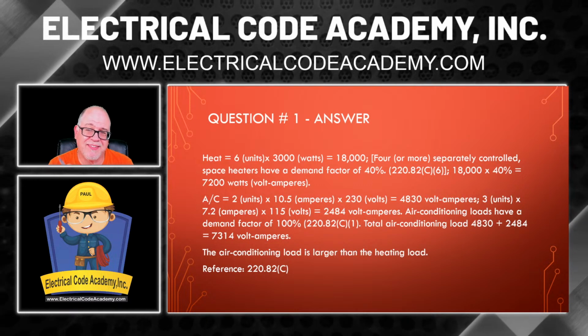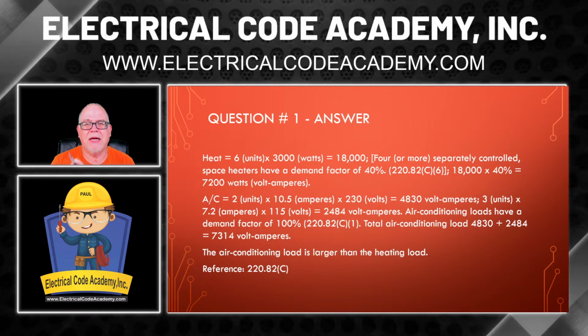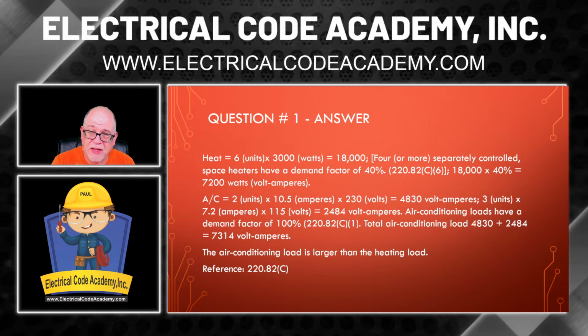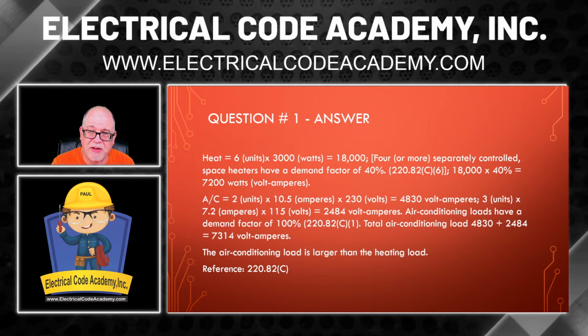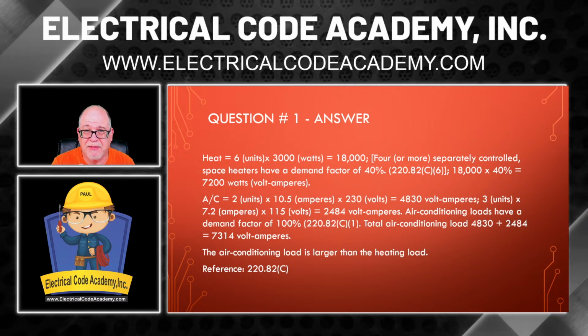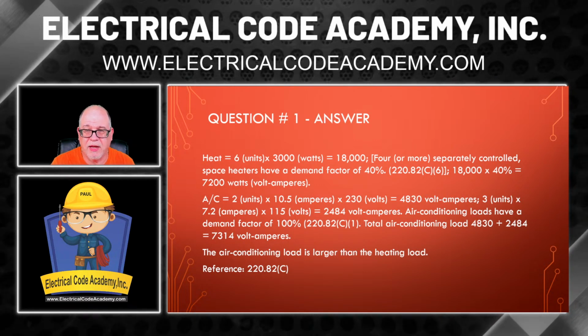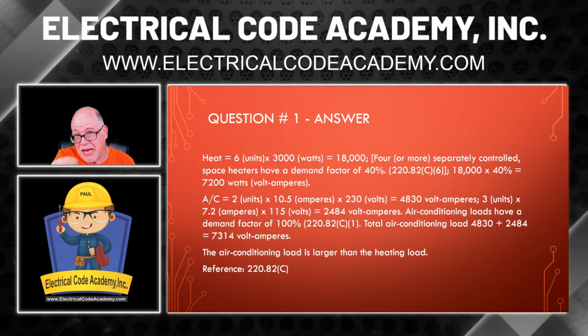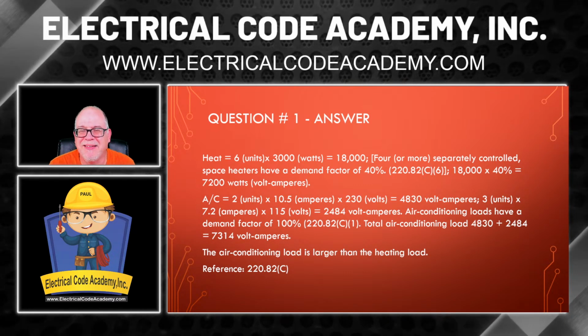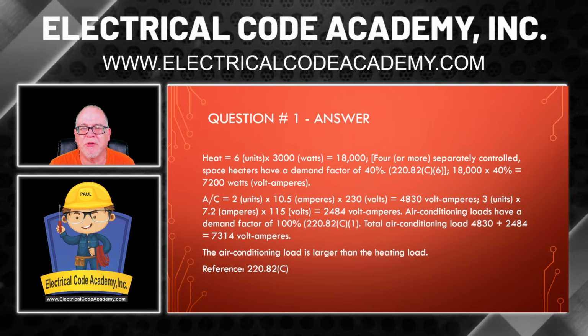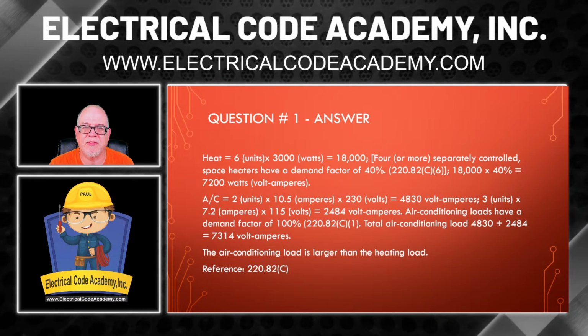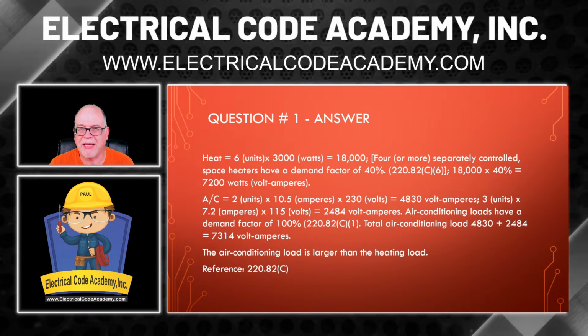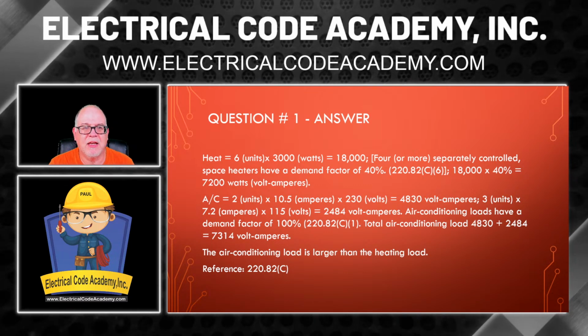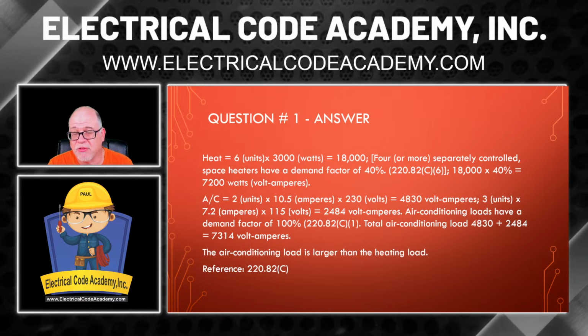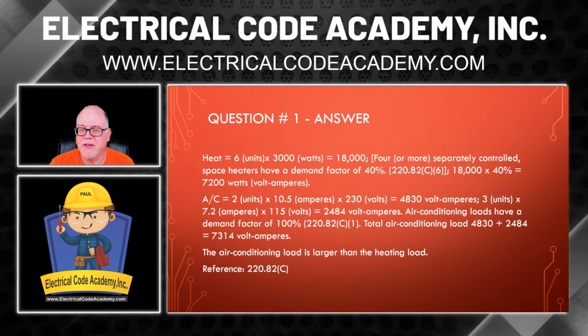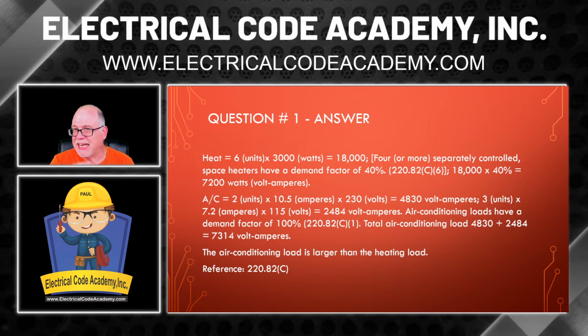Now, remember what it said? It says we take it... Now, this says 220.82(C)(6), but actually, which one was it? It was (5) that we're using for the heat. Okay, so typo. So we're doing 18,000, and we're going to multiply that by 40%. That gives us 7.2 kW, or in our case, since we worked it out in watts, it is 7,200 watts, or 7,200 VA.